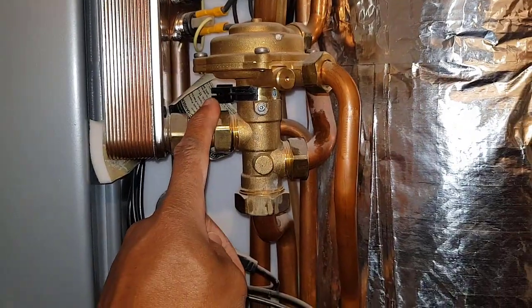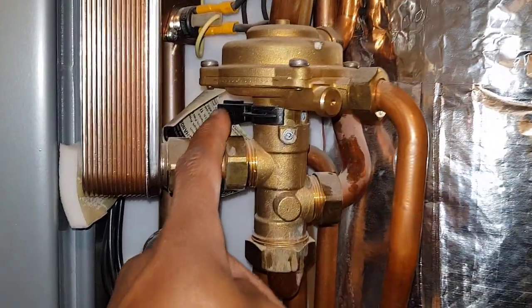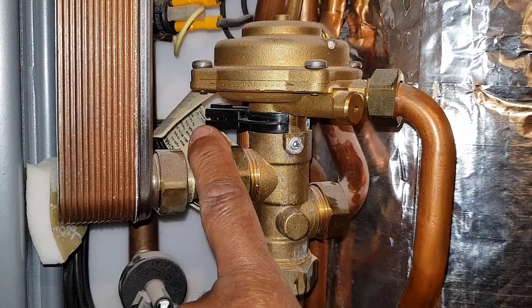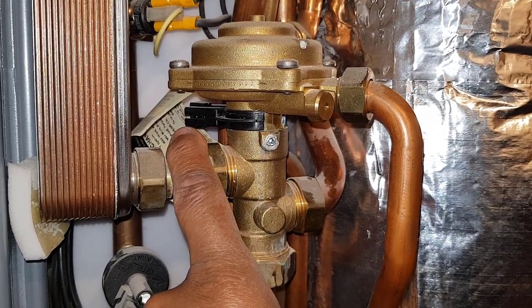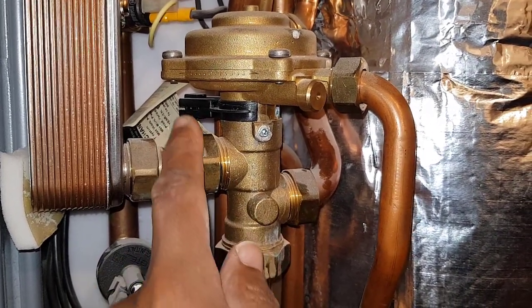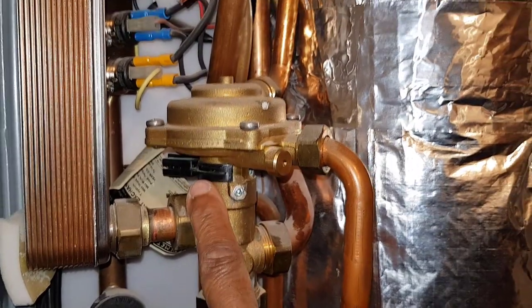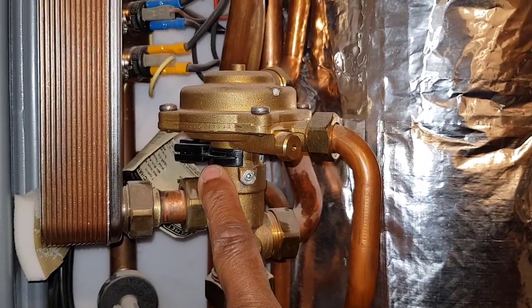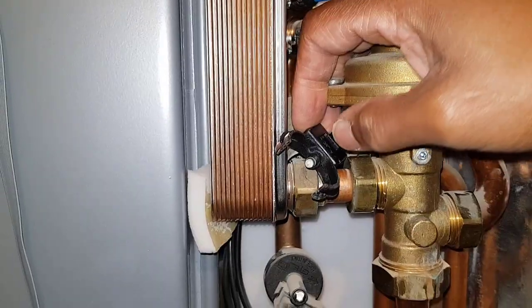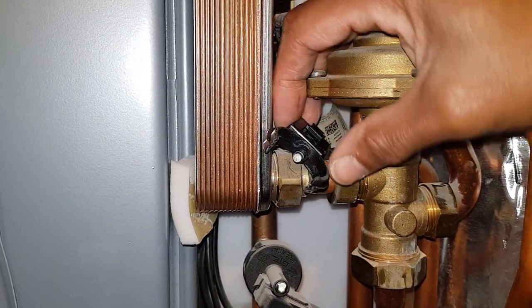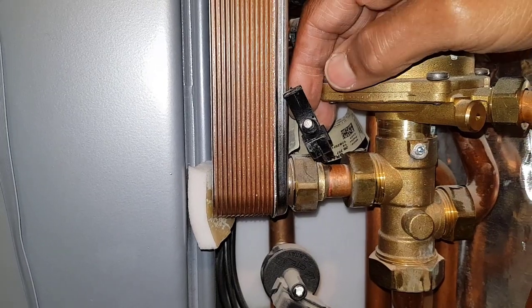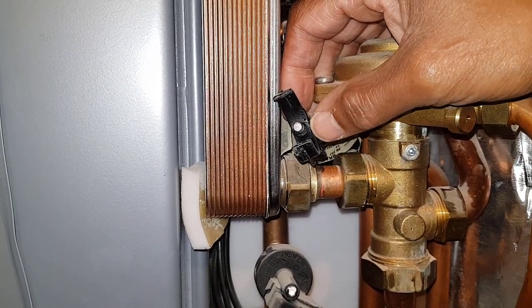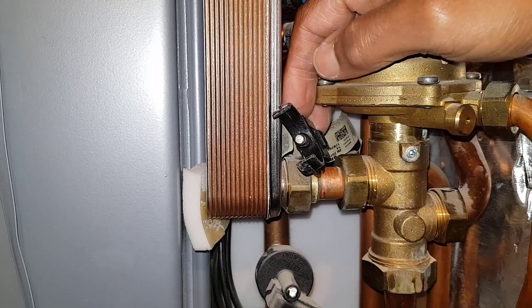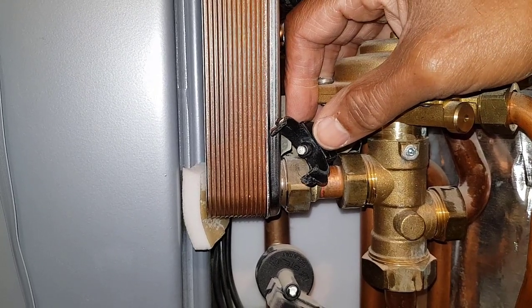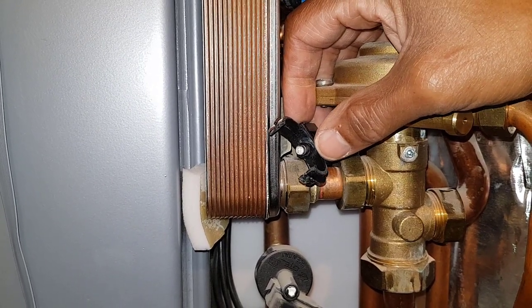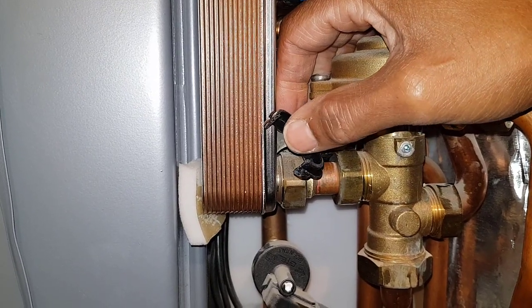This is the diverter valve, and then you've got this micro switch which connects to the diverter valve. What's happening is, if I pull that switch away from the diverter valve, the pump will stop. So what I've done now is pulled this micro switch off the diverter valve. I think we've got a double problem: either the diverter valve's damaged the switch, or the switch is damaged. So watch what happens now when I push that in. Listen.